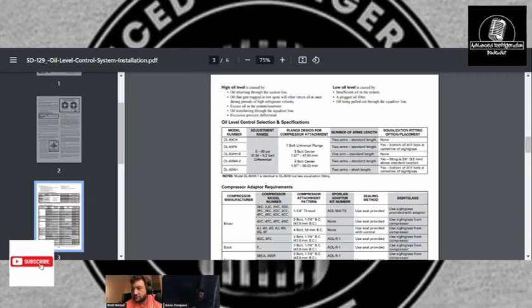That's why it's super important to make sure these oil levels are 100% correct. I'm not a big fan of oil equalization - I think it causes more problems than it solves most of the time. One compressor takes out the entire rack, or locks up the entire oil system if it has blow by. But they do have their place at times to fix the compressor that keeps filling up. I'm a big proponent of asking why the oil is leaving the compressor so much. Usually when you see that, you have oil separator issues, or load issues, or a typical centrifugal oil separator with 40% rack load.